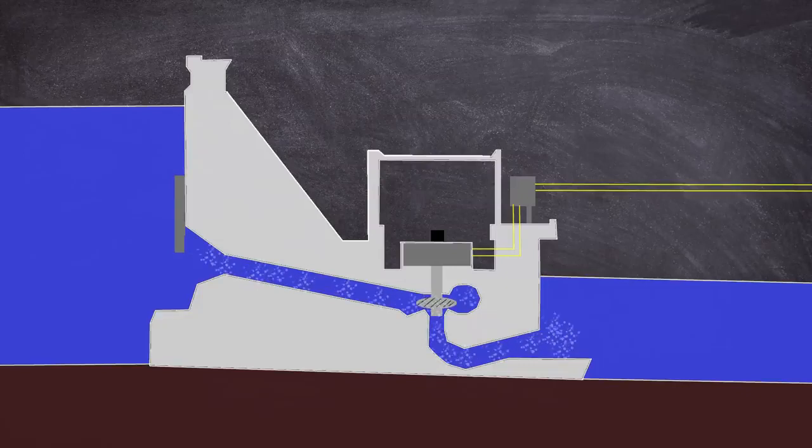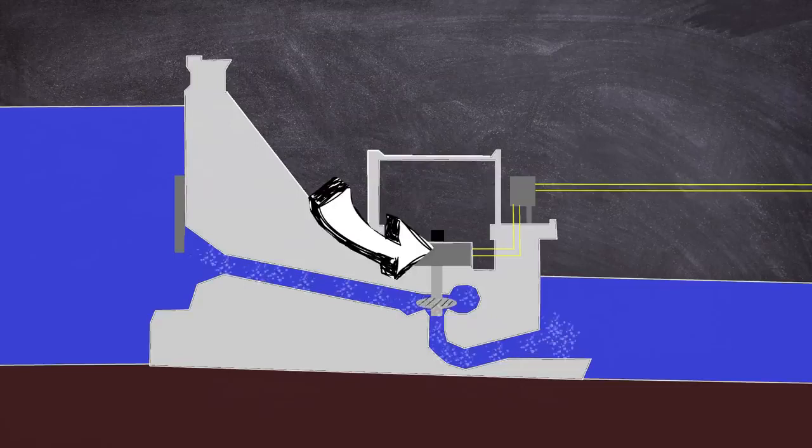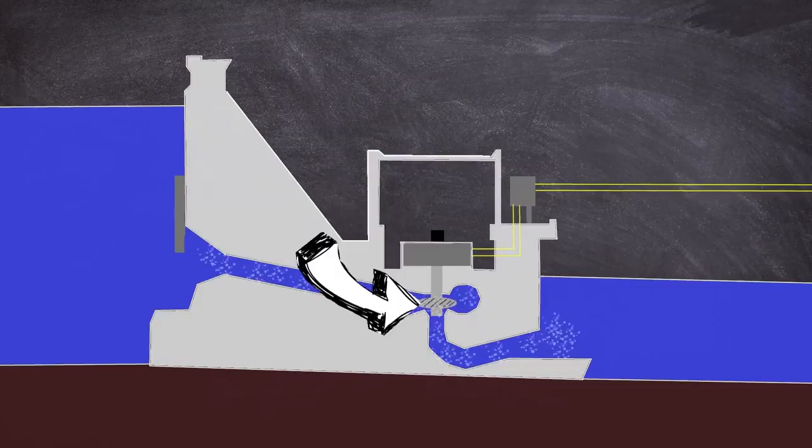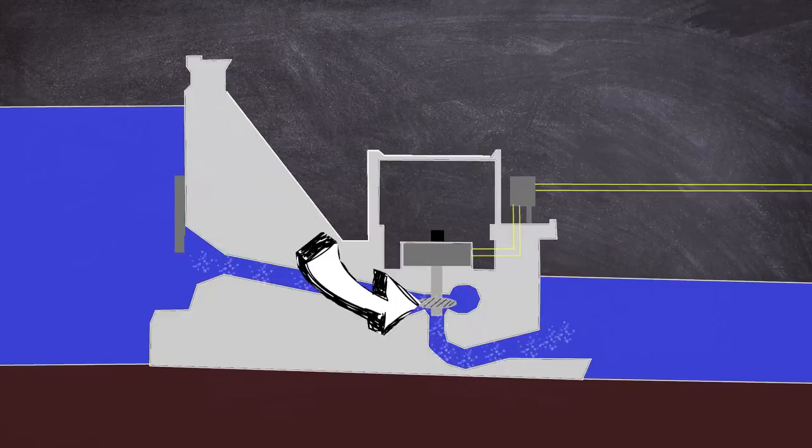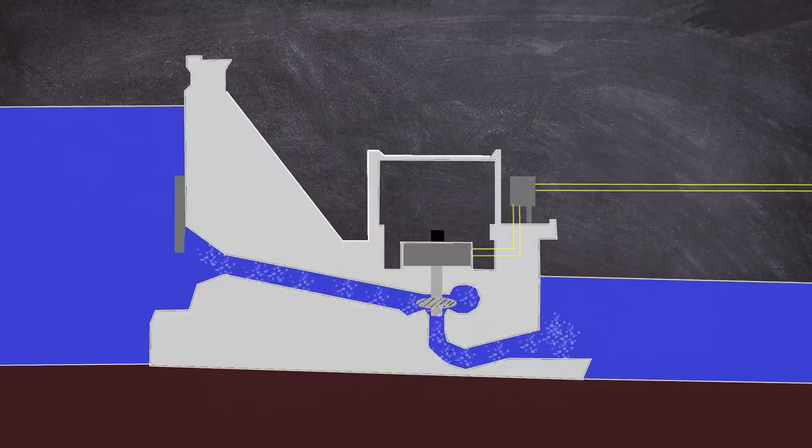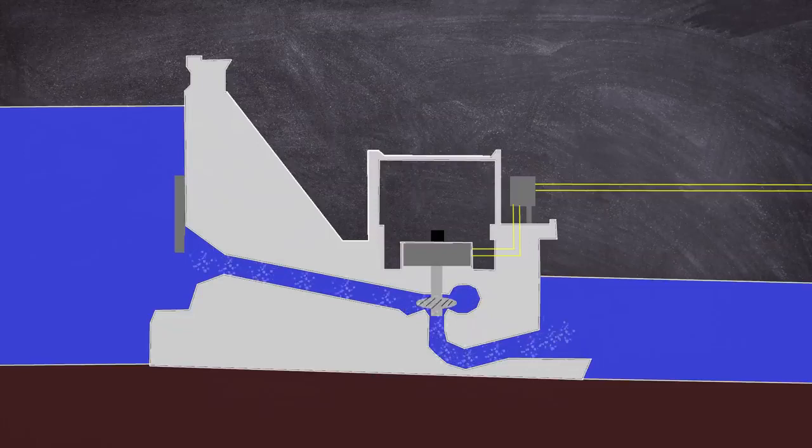The water has a high energy caused by the weight of the remaining water inside the reservoir. The water is passed through a turbine which in turn rotates, turning a generator. For the fine tuning of the power produced by the plant, wicket gates are used, and these surround the turbine. More or less power can be generated by these gates regulating the water flow and are vital in keeping control of the desired output. These gates can be closed completely, essentially bypassing the turbine. After all this, the water is passed to an outlet gate to resume its flow down the river.